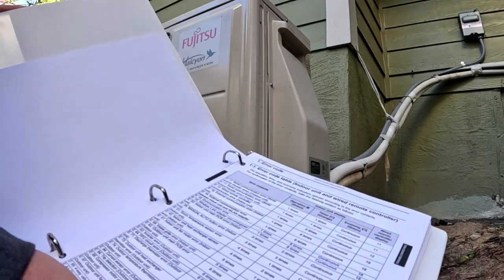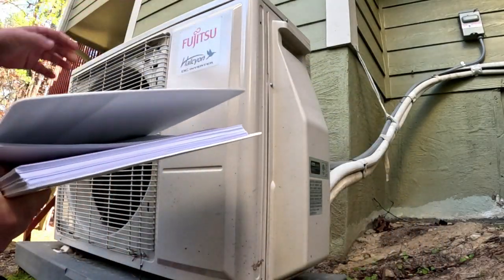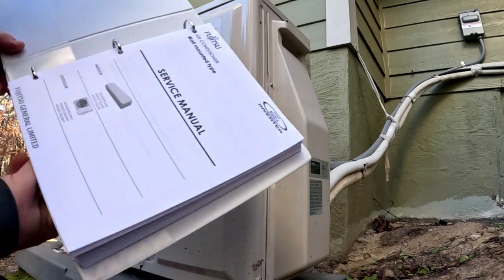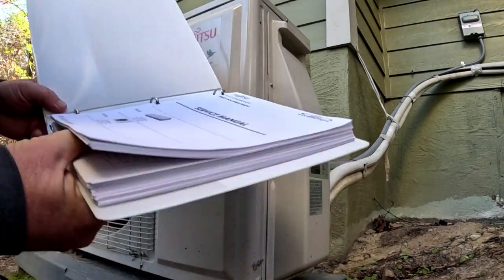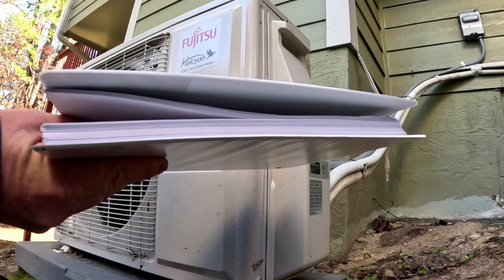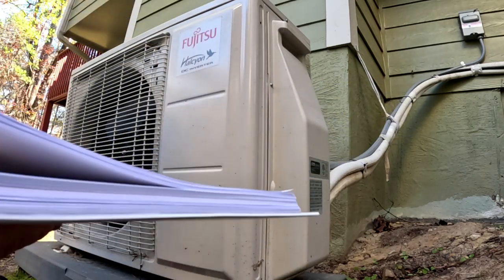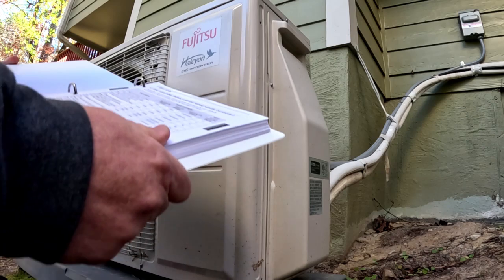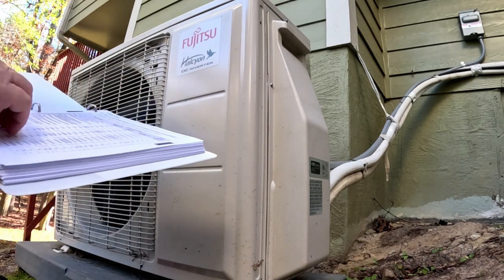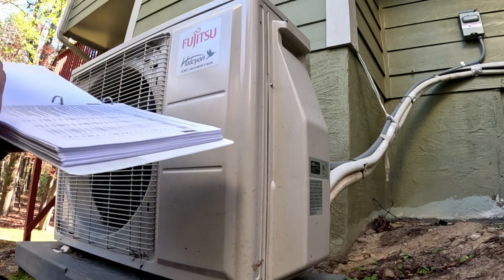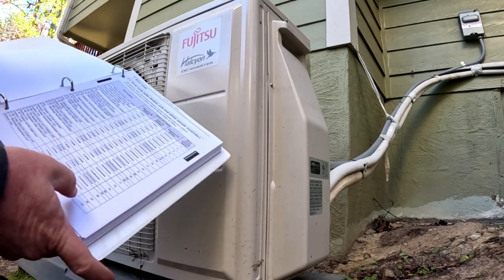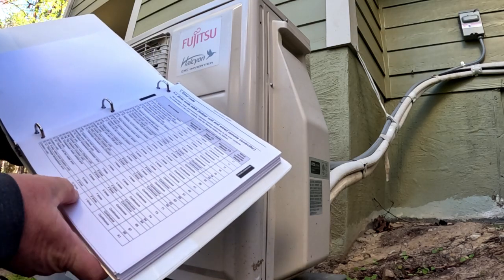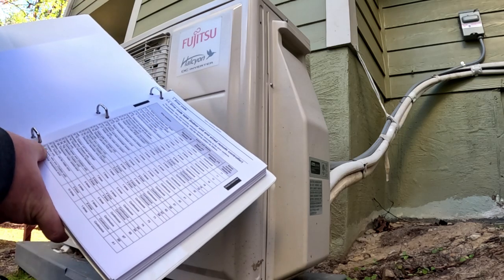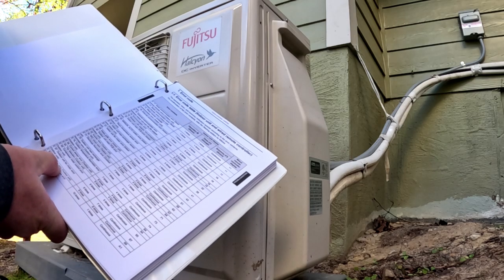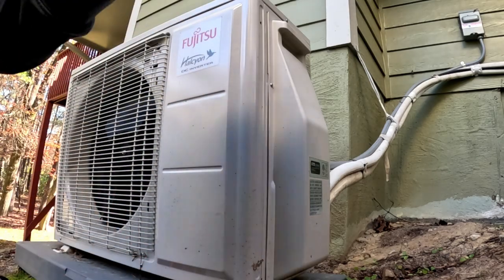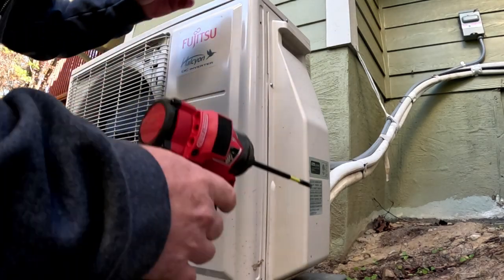So I have some books I printed out for some of these mini splits. Just the manual for this one, which covers the indoor and outdoor unit, is 171 pages. Go figure that. So anyway, these are the indoor error code tables. And if you saw that, we had a continuous flash on that light to the right. 9 green, 9 orange, which is an E99 4-way valve error in the outdoor unit. So we're going to get this thing opened up.